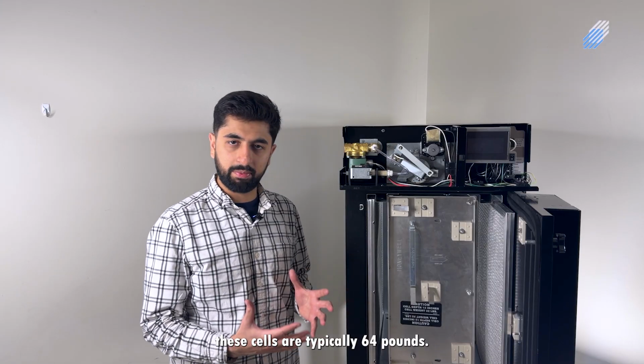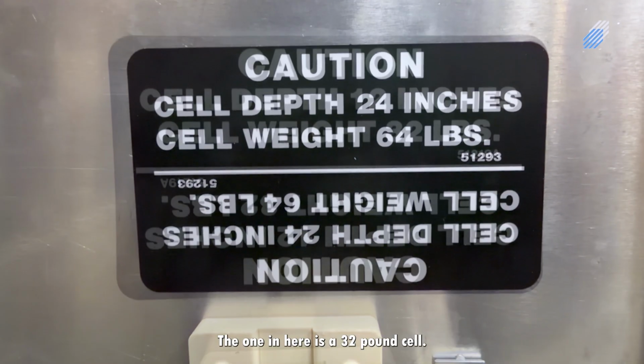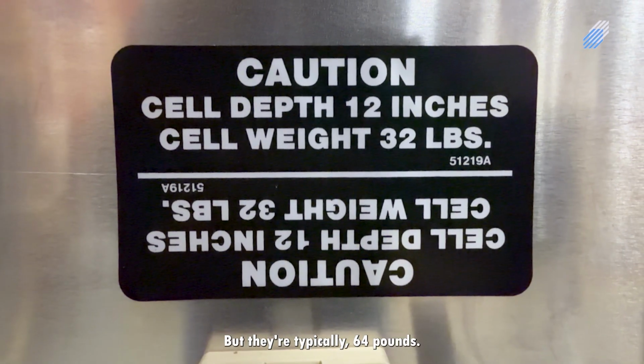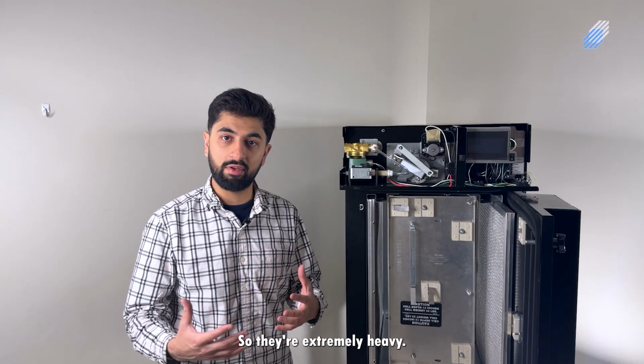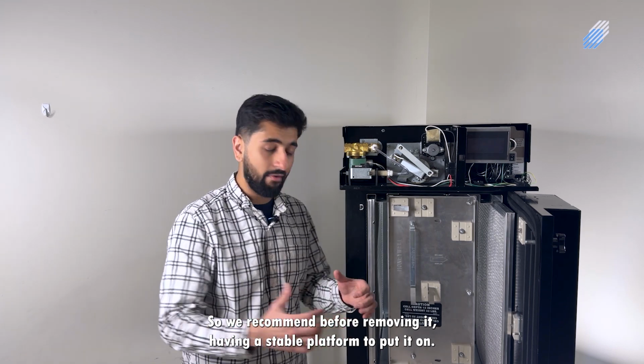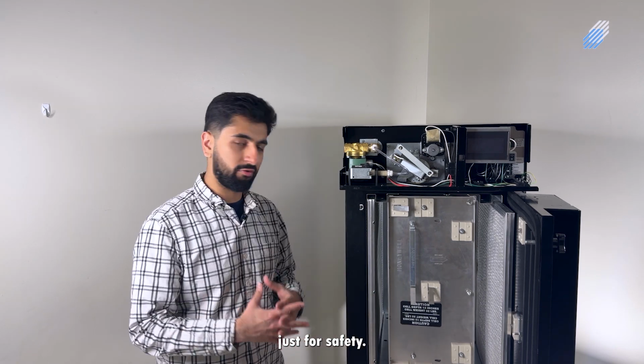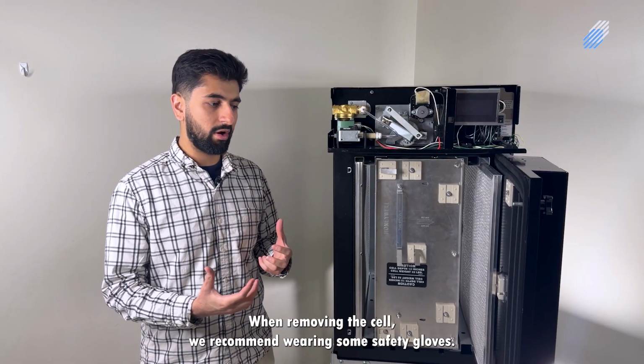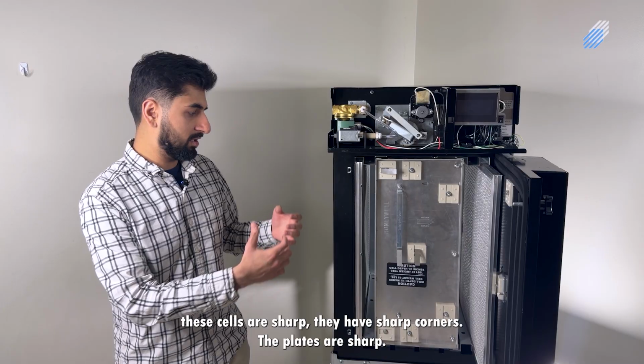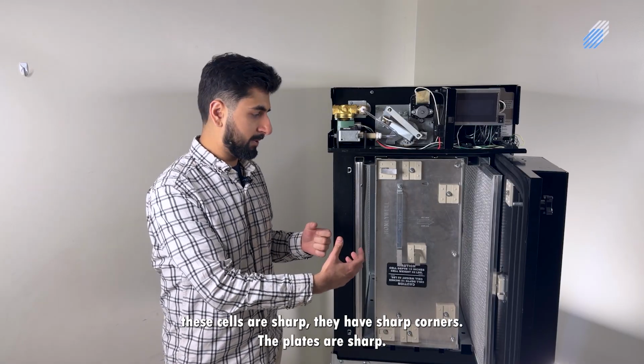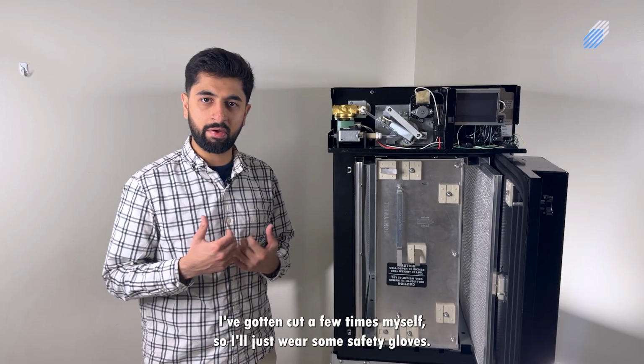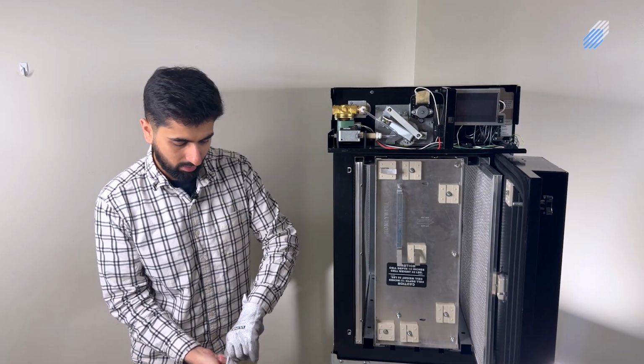These cells are typically 64 pounds. The one in here is a 32-pound cell, but they're typically 64 pounds, so they're extremely heavy. So we recommend, before removing it, having a stable platform to put it on, just for safety. When removing the cell, we recommend wearing some safety gloves. These cells are sharp. They have sharp corners. The plates are sharp. I've gotten cut a few times myself. So just wear some safety gloves like this.